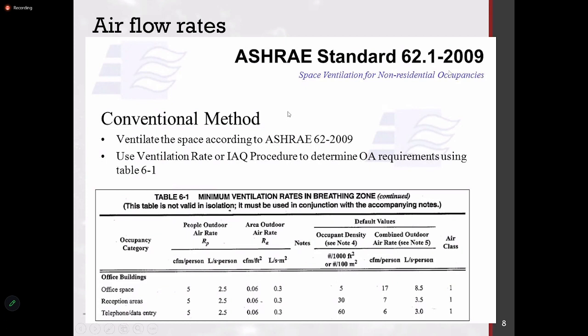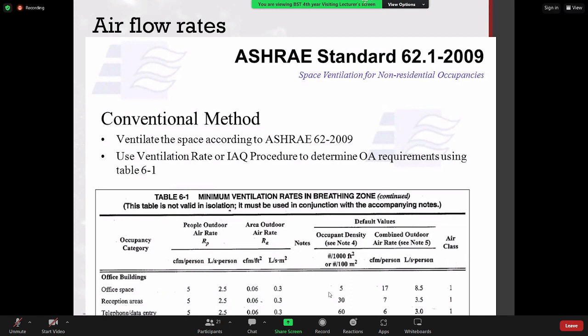So they calculate based on two parameters. One parameter is the area, how much area you need to ventilate, and how many people are actually inside that room. So depending on different requirements, now this is particularly for office building, so office space, reception, there is telephone and data entry also, but the same figures apply. So depending on the requirement, you have to increase or decrease the ventilation.